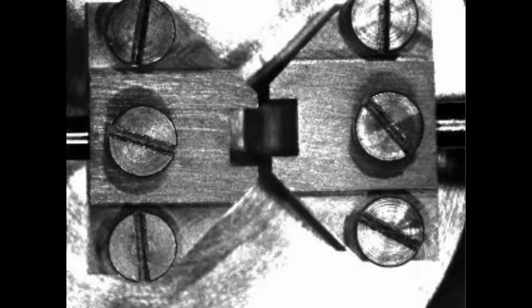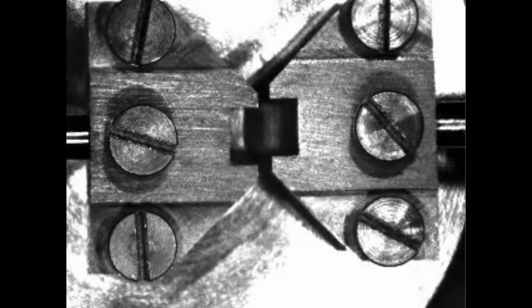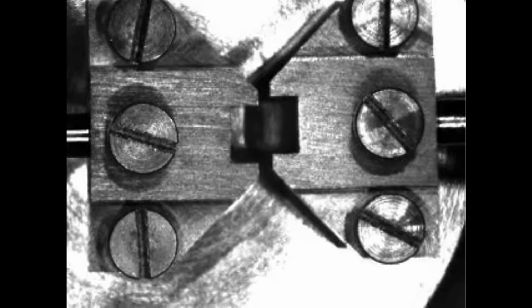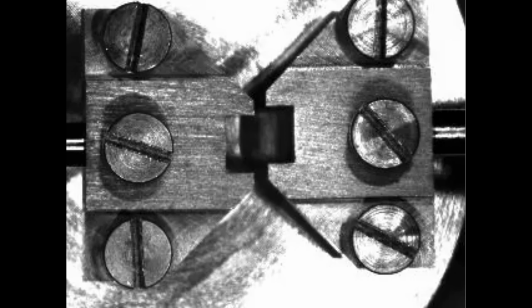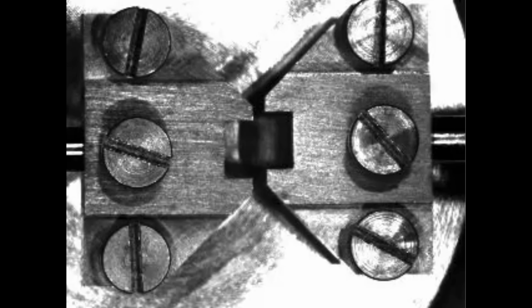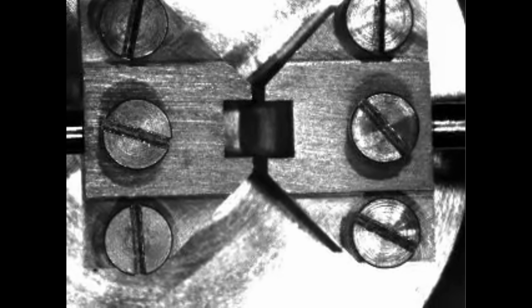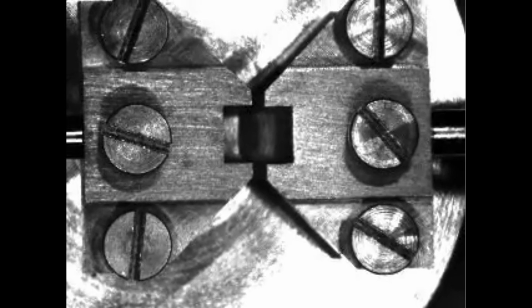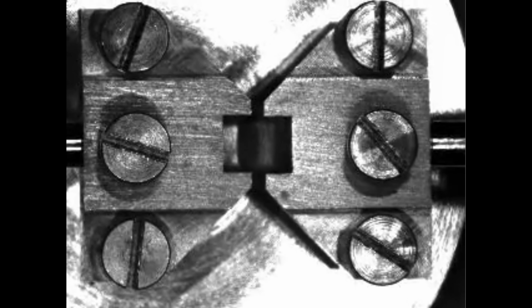We will start by showing alignment of the jaws. You should start by making sure the transducer side jaw is flat and level in the chamber. In this case, the right side is the transducer and it is flat and level. Start the alignment by loosening the screw under the black cover. You can get the alignment close, starting here. Tighten the screw back in place.